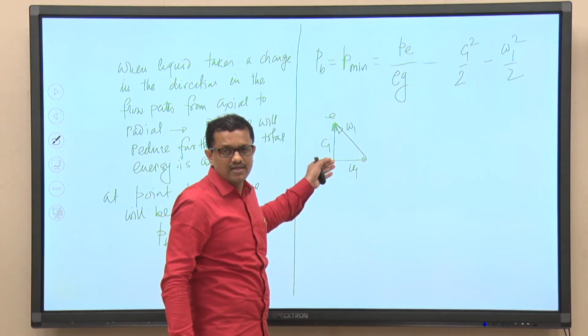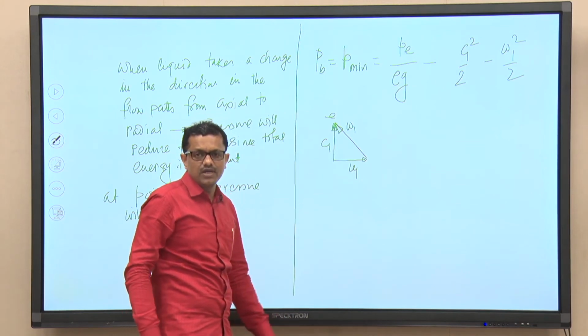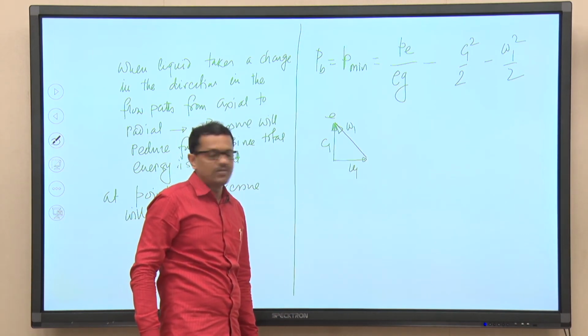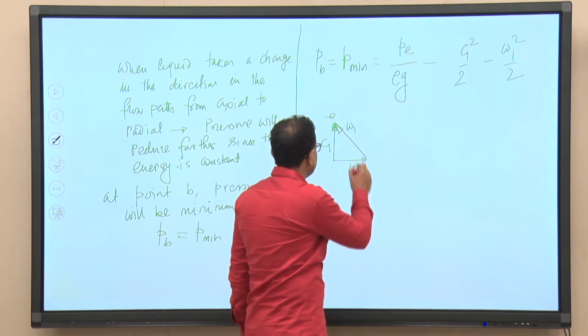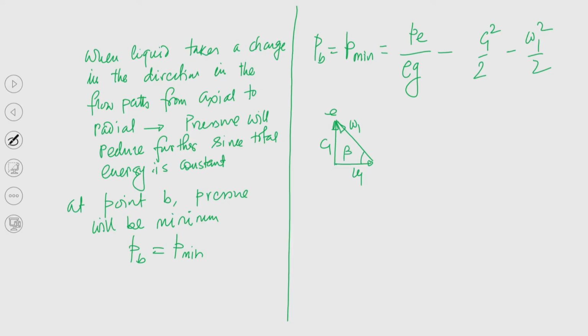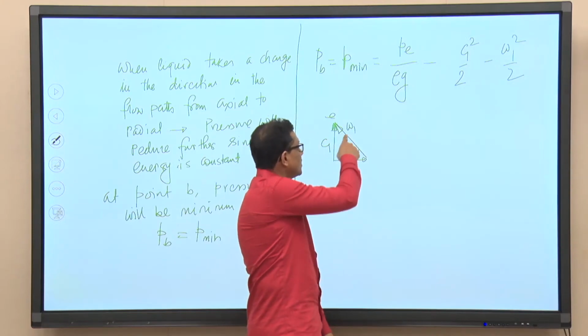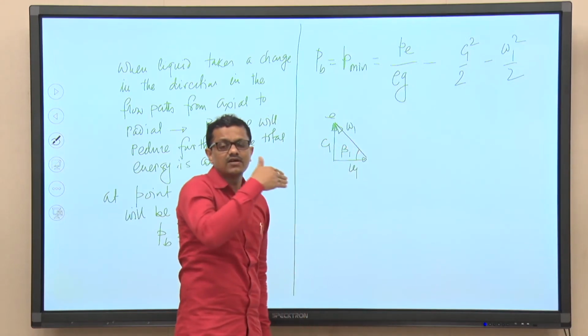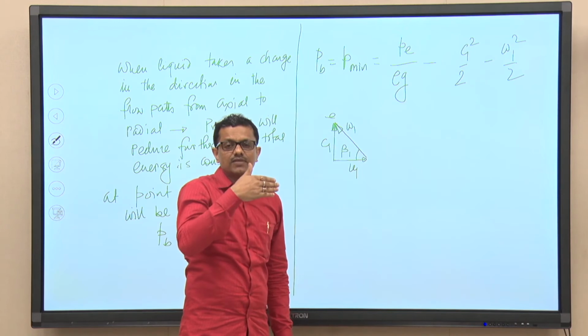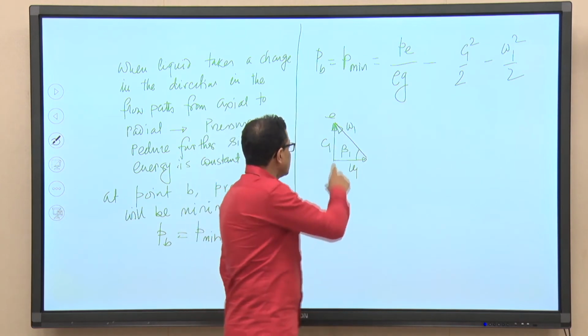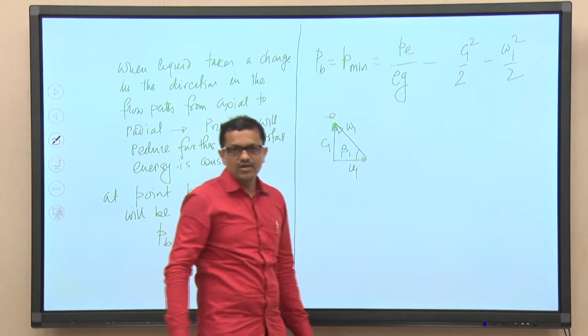We have drawn this velocity triangle so many times while we have discussed the radial flow pump and also the total head developed by the pump. Now, this angle is known as beta 1, that is the blade angle at the inlet. You can see that C1 has a magnitude at the inlet, at point E, and W1 also. So, basically U1, the tangential component velocity, is fixed. W1 is the relative velocity, that is the velocity of the fluid relative to the blade, and the resultant is the absolute velocity, that is what we have discussed, right.